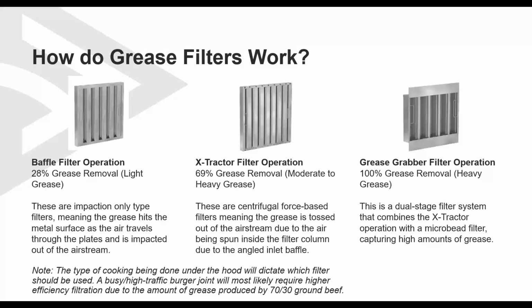Next, we have our X-Tractor filter. At about 69% grease removal, we consider this a moderate to heavy grease use. These are centrifugal force-based filters, meaning that the grease is tossed out of the airstream due to the air being spun inside the filter column due to the angled inlet baffle.